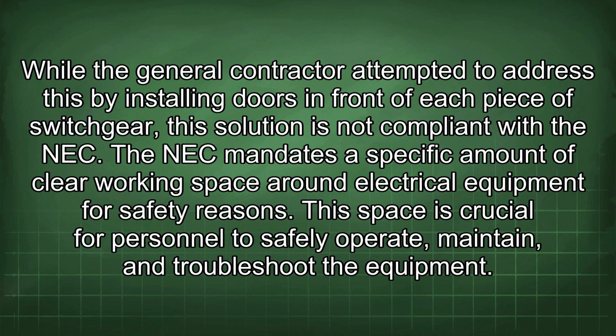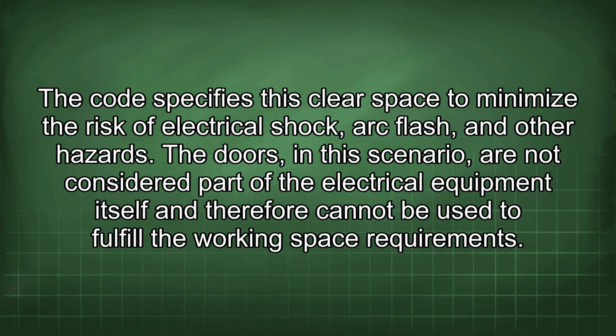The NEC mandates a specific amount of clear working space around electrical equipment for safety reasons. This space is crucial for personnel to safely operate, maintain, and troubleshoot the equipment. The code specifies this clear space to minimize the risk of electrical shock, arc flash, and other hazards. The doors, in this scenario, are not considered part of the electrical equipment itself and therefore cannot be used to fulfill the working space requirements.